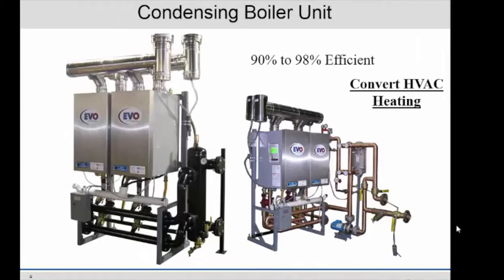What we look at is we get rid of steam, if we can. Big central steam plants that they have are very inefficient, okay? So we try to go to distributed heat, where we'll have a building out here that needs some kind of heating, and we try to put in a condensing boiler. This is a condensing hot water boiler to provide the heating hot water more efficiently. It can also supply the hot water to the processes. It's got everything mounted on here, and you're getting efficiencies of 90 to 98%, compared to central steam plants, 50% if you're lucky. When you add it all up and look at the seasonal efficiency, you're just wasting a lot of energy.